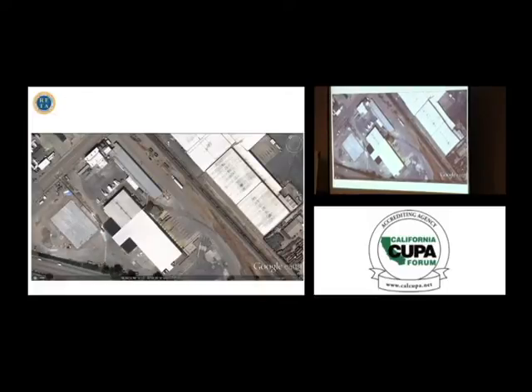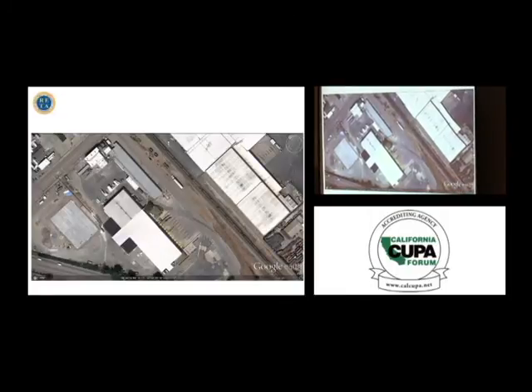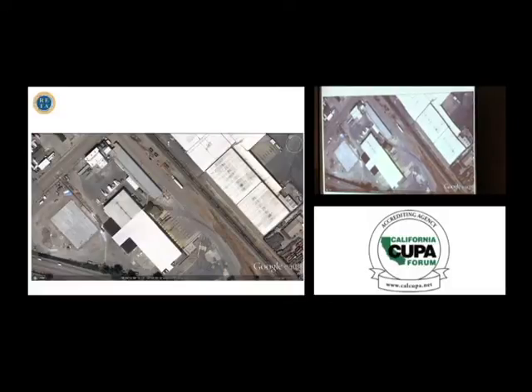The biggest part of the building is refrigerated with a nominal quantity of refrigerant, about 5,000 pounds. There's a third system here where there's a refrigeration compressor and condenser right here adjacent to the building that provides refrigeration for equipment that comes and goes on a seasonal basis. About 2,000 pounds there. And then the normal charge over here is, again, about 7,000 pounds. So no one system exceeds 10,000 pounds, but this facility chose that because they all have a thing in common. If a fire happened here, all three systems are active in the same general location, so they are treating the facility as a Program 3 CalARP RMP PSM facility, even though it could be argued we have co-located separate systems. But a fire here will make a problem in all three locations, so we're doing RMP there.